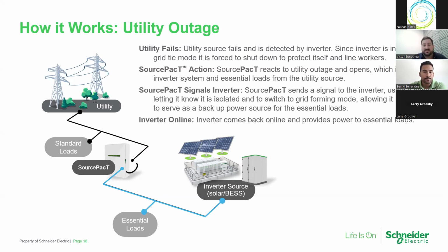It'll then send a signal from SourcePacT, from the isolation device, over to the inverter, dry contact, letting it know, hey, you're isolated. It's safe for you to switch from grid tied mode, where you have to be shut down, to grid forming mode, which means you can come back online and you're essentially the only power source on that bus at that point in time. And you're going to operate in this mode not indefinitely, but until you exhaust the charge on your batteries, or until you run out of solar power for whatever reason. You'll run on that until either you exhaust your energy sources or until utility power returns. Next slide.